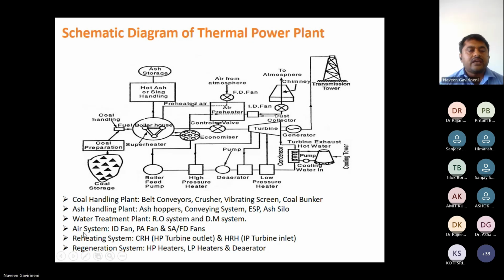There is an air system, which I have already explained, ID fan, PA and SA fans. Sometimes in some places it is in SA fans, sometimes it is in FD fans, but both give the same purpose. Then the next cycle is the reheating cycle. As I have explained in an earlier slide, there is a CRH and HRH arrangement, cold reheat and hot reheat. The next cycle is the regeneration system, HP heaters, LP heaters and deaerator.